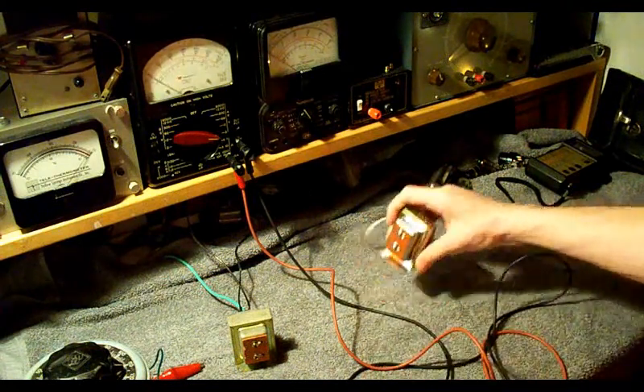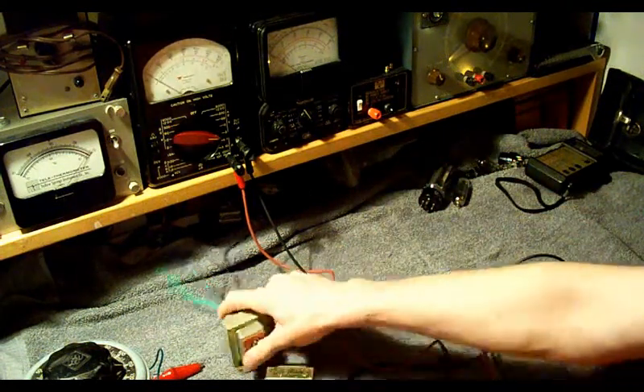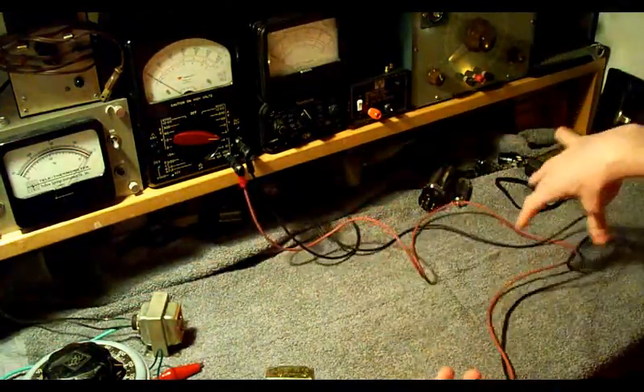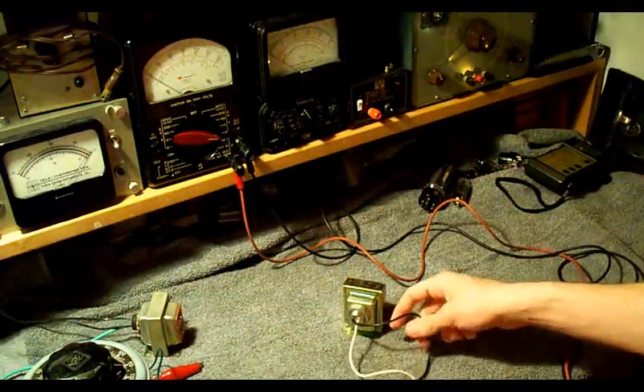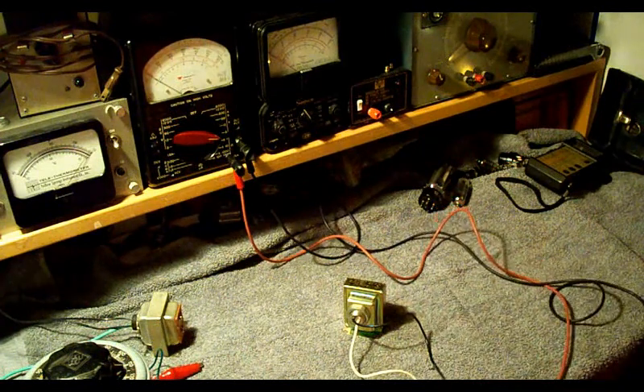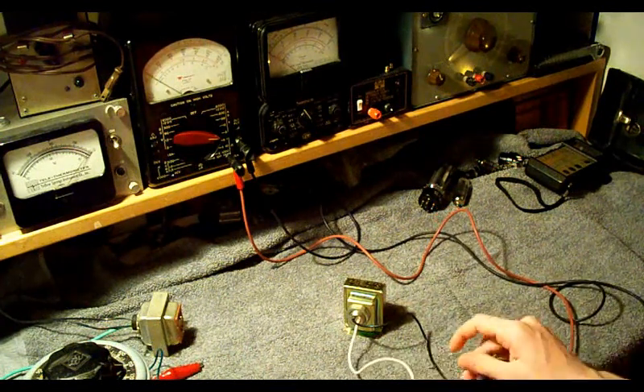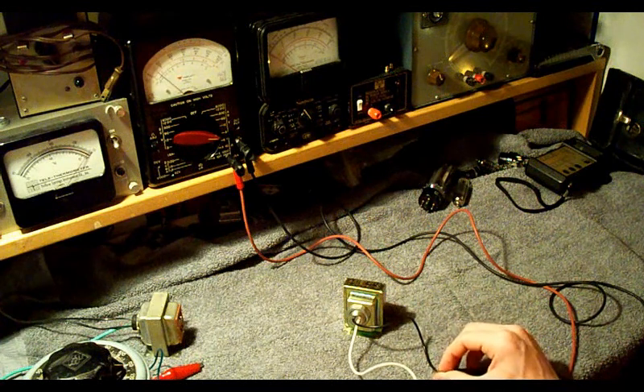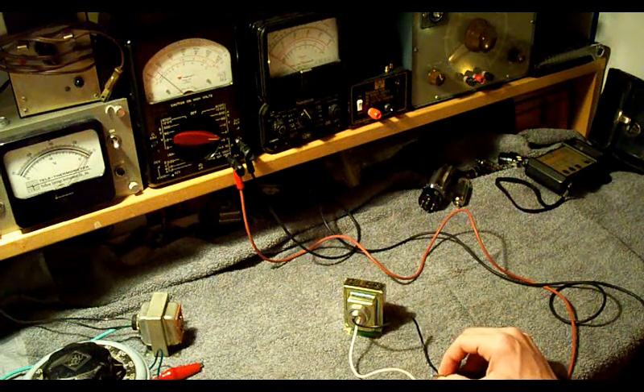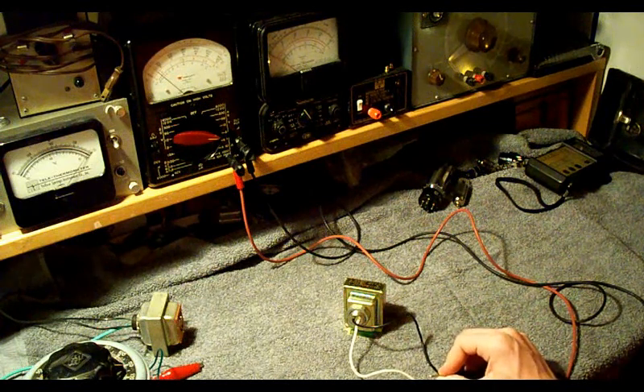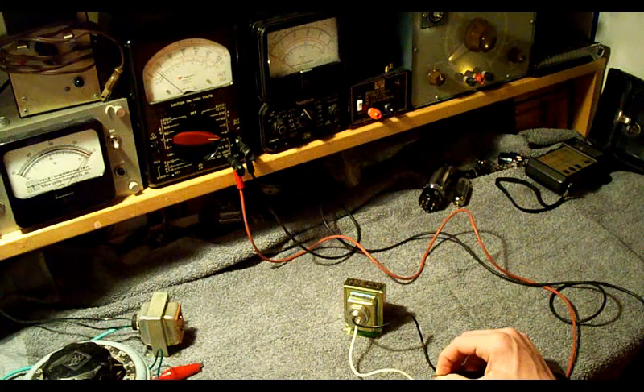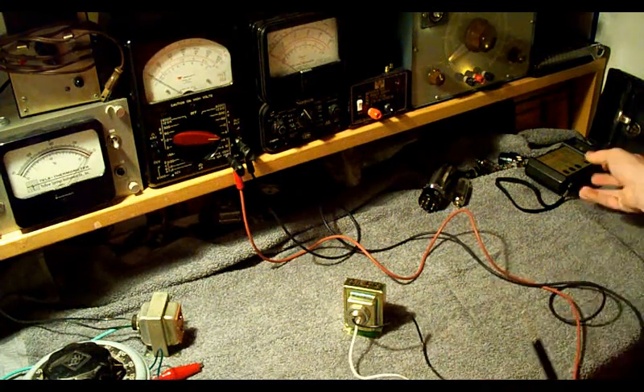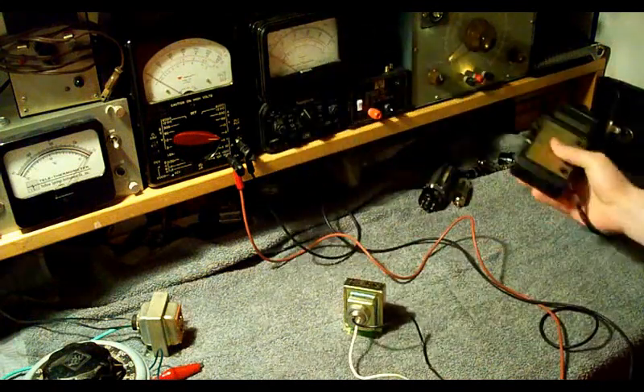Now when we test this transformer, first we're going to test this one. So the first thing that we want to do to test this transformer is we're going to check across the primary winding. So we're going to check right across the primary. And that's good. We're reading about, well, let's see here. The scale goes, well, that's good. We know it's not 0 ohms, so we definitely have continuity there, and the resistance is not excessively high. So this transformer is reading good. And I will also be demonstrating on a digital meter as well shortly.